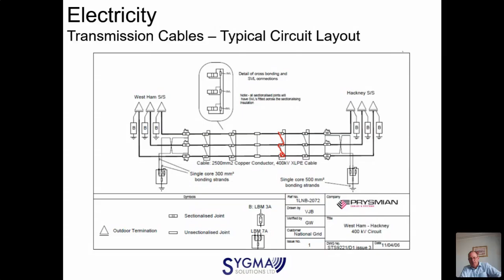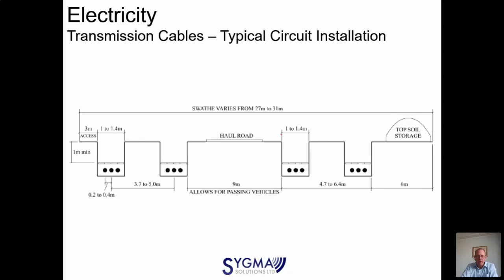So this came from National Grid. It gives you an idea. You might be using your GPR to find these. According to National Grid, there will be 1 meter minimum cover. Whether this is the case or not is anybody's guess. You've then got roughly a width of about 1 to 1.4 meters where the cable is going to be installed, then roughly between 3.5 and 5 meter separation. So if you look at that, that's the same kind of configuration as a pylon. It's just that it's buried in the ground rather than on a tower.